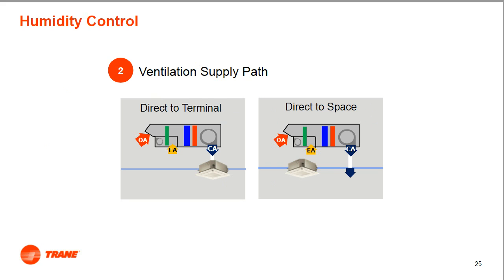Then, the next important step is to determine your ventilation supply path. The two main methods for doing so are either the direct-to-terminal method or the direct-to-space method. Some of the advantages of the direct-to-terminal method are that it helps to ensure that the required outdoor airflow reaches each zone. This method also avoids the cost and space it takes to install additional ductwork as well as diffusers. And it also has the ability to provide an even outside air distribution through VRF terminal units. Some disadvantages of this system are that the VRF terminal units must operate continuously to provide the outside air, and that measurement and balancing can be a bit more difficult during the commissioning of the system.